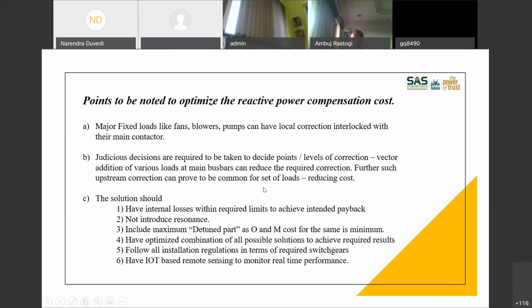See, we all know that we have huge distribution in our plants. You have the main HT incomer, then if you are an HT consumer, you have an HT to MV transformer, then MV is distributed to so many transformers, and then there are your end loads. All the load currents consumed by your various loads get vectorially added at the immediate upstream bus bar. So you get what we call a harmonic cancellation effect. You get a kind of reactive power compensation effect because some of the loads might need reactive power at some time, and some of the loads might go into capacitive mode. It is possible. Any one step you take to give correction to a group of loads, you get some benefit as far as reactive power compensation is concerned on your basic investments.